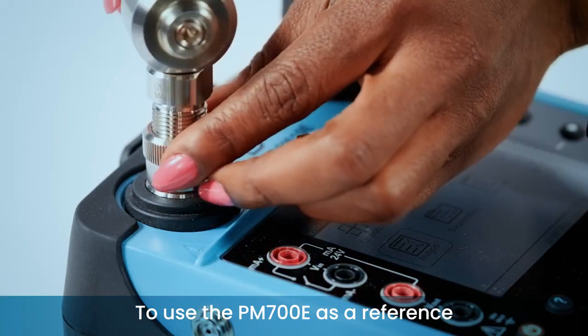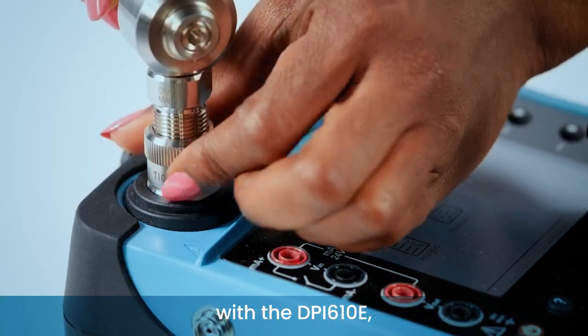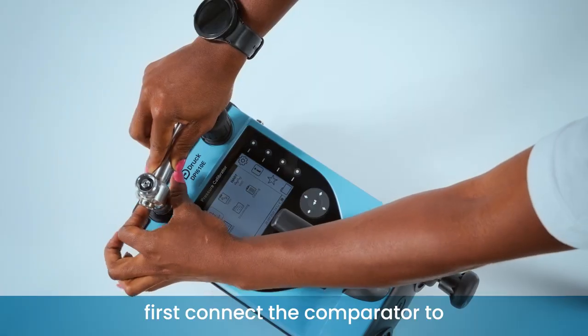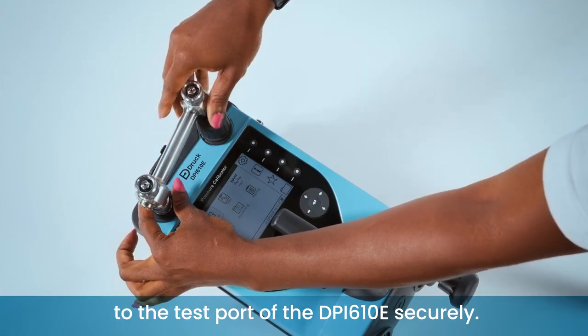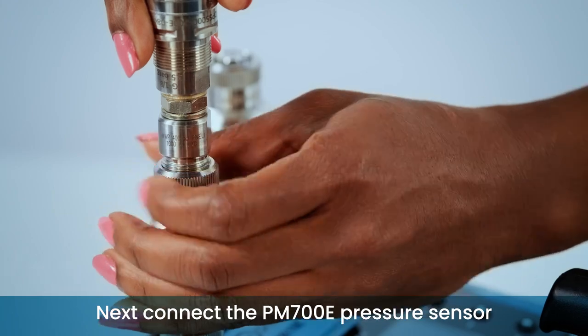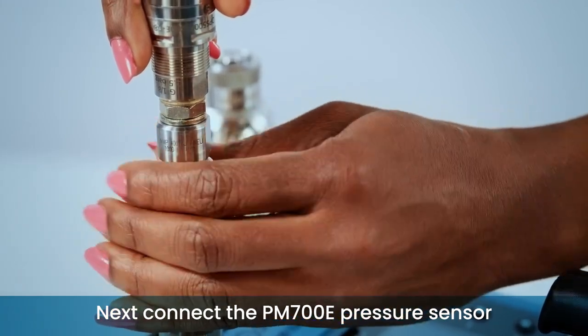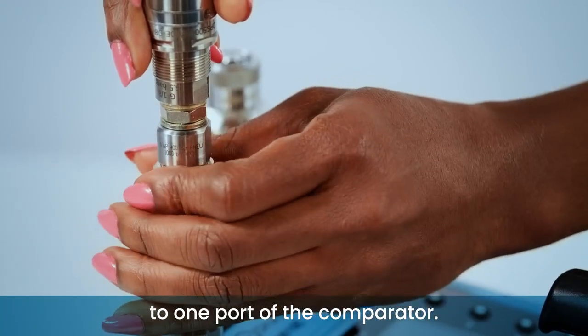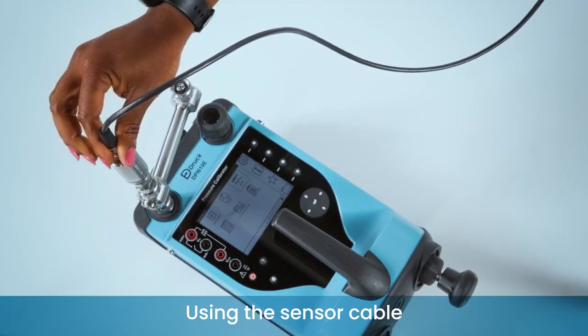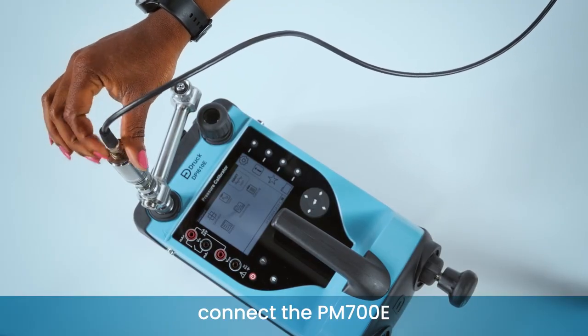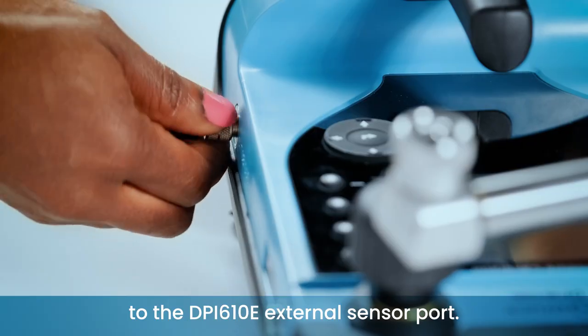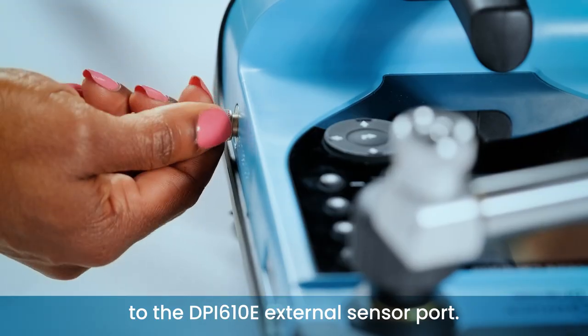To use the PM700E as a reference with the DPI610E, first connect the comparator to the test port of the DPI610E securely. Next, connect the PM700E pressure sensor to one port of the comparator. Using the sensor cable supplied with the sensor, connect the PM700E to the DPI610E external sensor port.